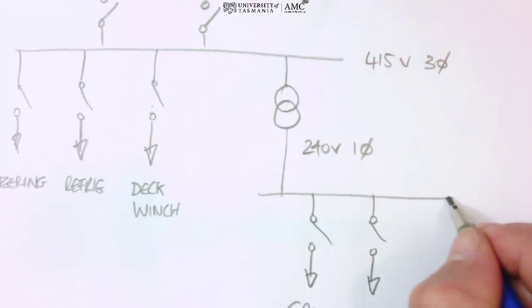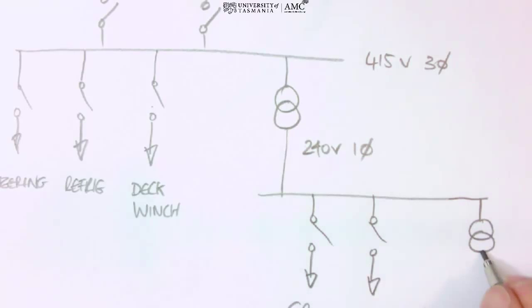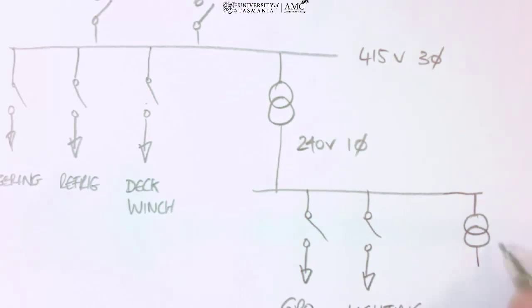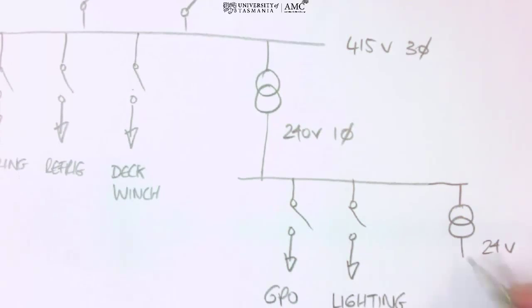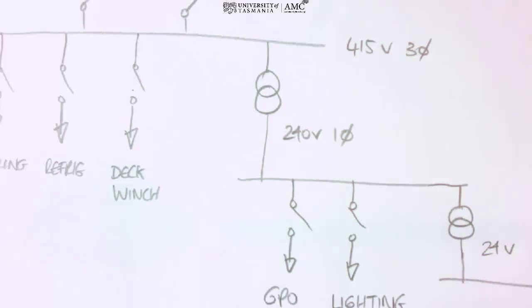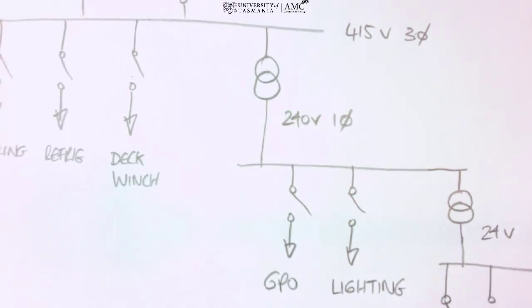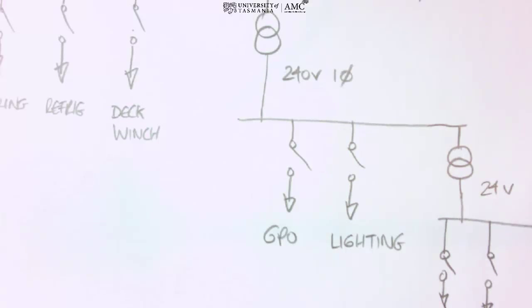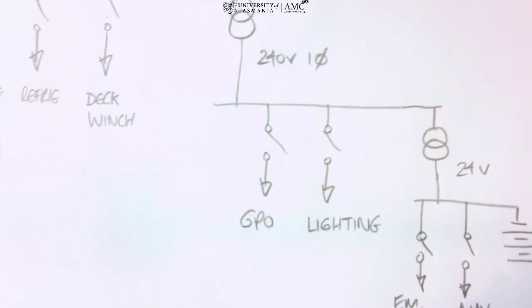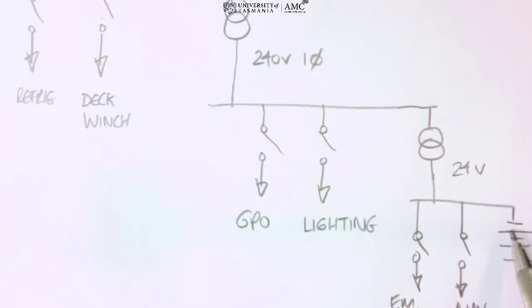Okay, and then on this end we're also going to have a transformer and a rectifier. What does a rectifier do? That changes the state. So we drop the voltage through our transformer down to 24 volts, but we're also going to change its state from AC to DC, and then that is going to supply another distribution board for all of our 24 volt emergency equipment. So things like our emergency lights, our nav lights, nav equipment, and then from here we're also going to have our battery bank, and we're also going to have a static charger which is going to keep our batteries charged.